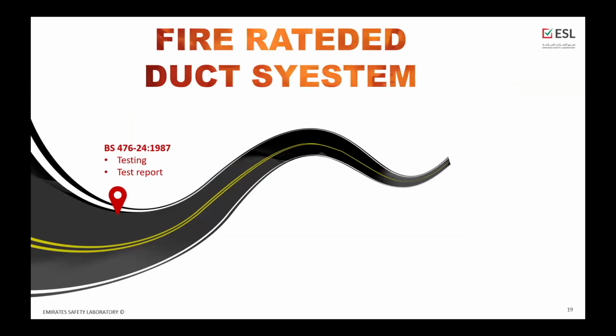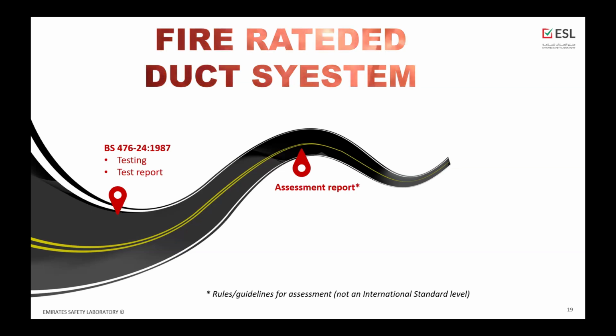So what is the roadmap for ducts tested as per BS and EN? If we are talking about BS, we have BS 476 part 24 from 1987. We do the testing, and as a laboratory, we issue the test report, which goes to the next step, the assessment report. The assessment report is based on rules or guidelines for assessment, which are not at the international standard level.